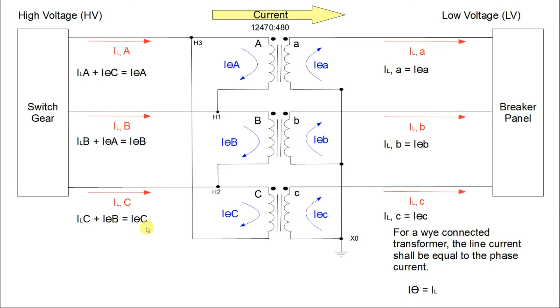For a balanced delta-connected transformer, the line current shall be equal to the square root of 3 times the phase current. Again, this is for a balanced delta-connected transformer. So my line current equals the square root of 3 times my phase current. If we get out of balance, we'd have to look at vector diagrams and things like that, which we don't want to get into today.